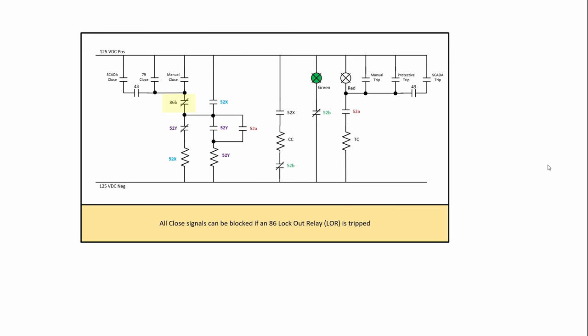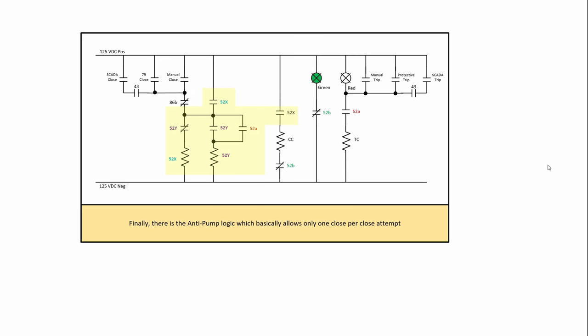86Bs are from a lockout relay. Lockout relays are tripped because of bus or transformer faults or breaker failures. So if they operate, we do not want to close. So we'll interlock the close of that. The anti-pump logic is right there. We're going to get more into that later. Note if you don't have anti-pump logic you could possibly close into a fault and then you could keep closing into it and we'll talk a little bit more about that later.